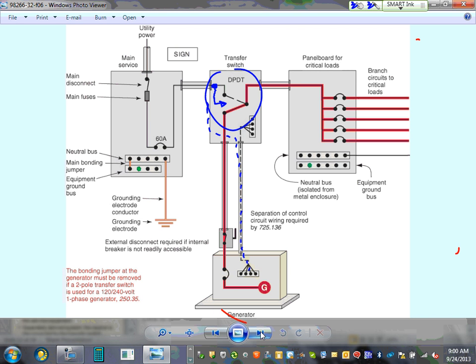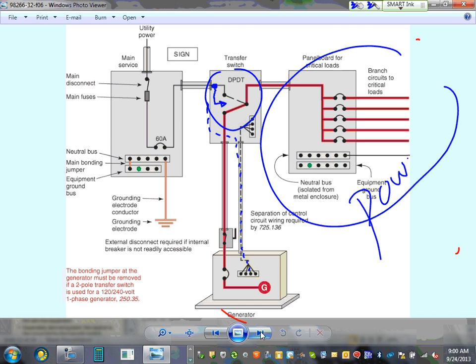The auto transfer switch sends the signal, fire. They fire. You don't have to go fire the generator. The generator will automatically start. The generator starts pumping voltage. When it starts, it also flips the switch the way you're looking at it here. Now, everything here is powered by your generator. Any comments, guys? Any questions? That's what we do in a dwelling. What you're looking at right now is how they do it in commercial too, for the most part.